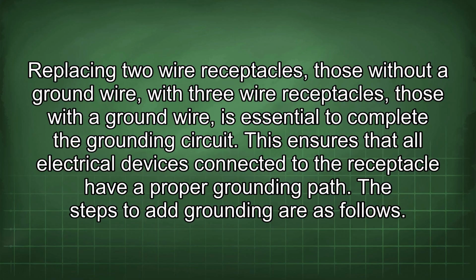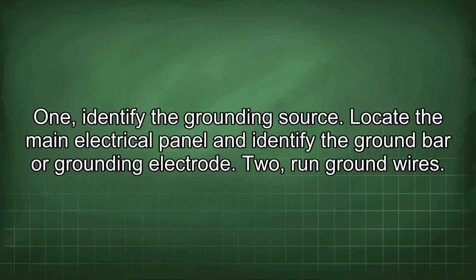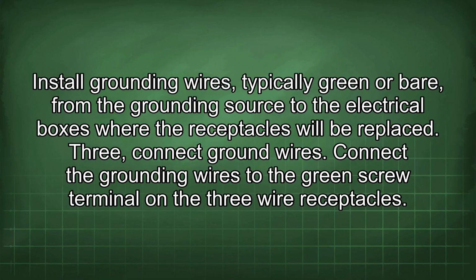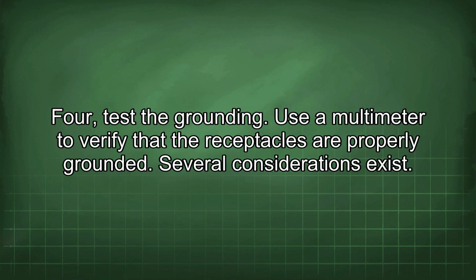The steps to add grounding are as follows. 1. Identify the grounding source. Locate the main electrical panel and identify the ground bar or grounding electrode. 2. Run ground wires. Install grounding wires, typically green or bare, from the grounding source to the electrical boxes where the receptacles will be replaced. 3. Connect ground wires. Connect the grounding wires to the green screw terminal on the 3-wire receptacles. 4. Test the grounding. Use a multimeter to verify that the receptacles are properly grounded.